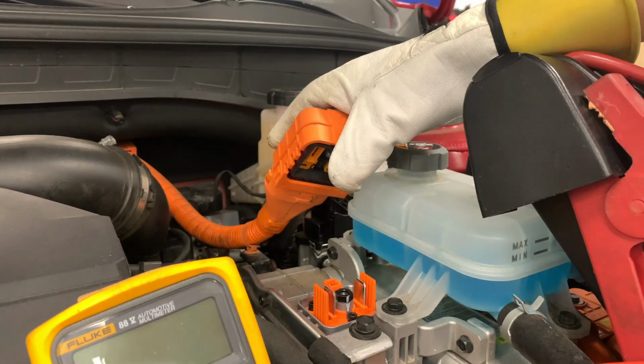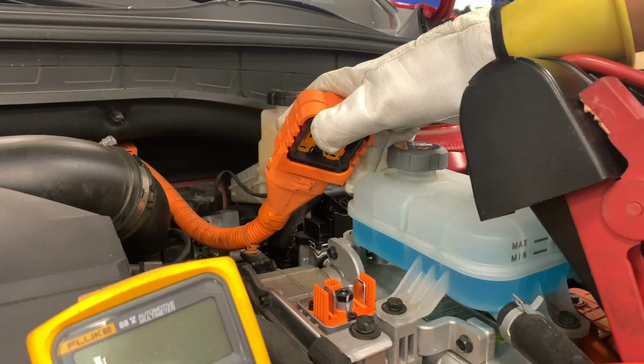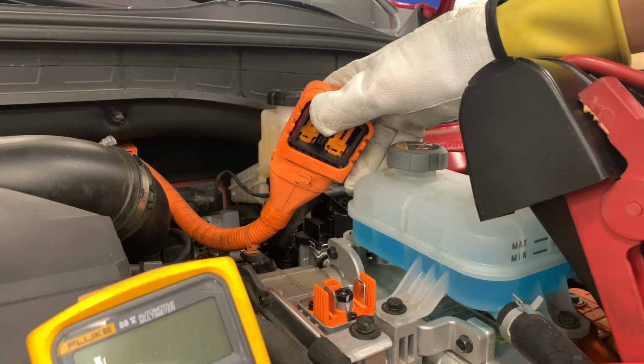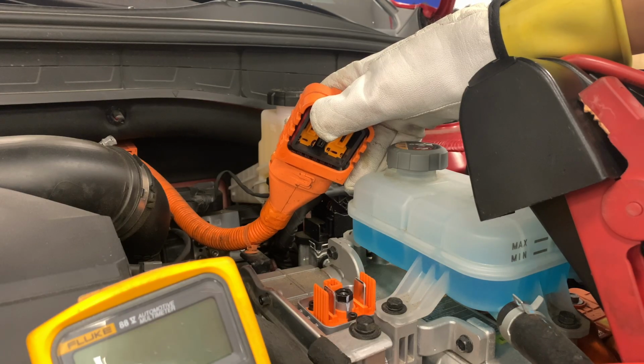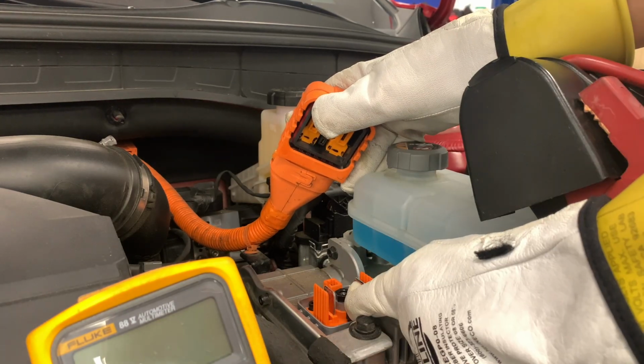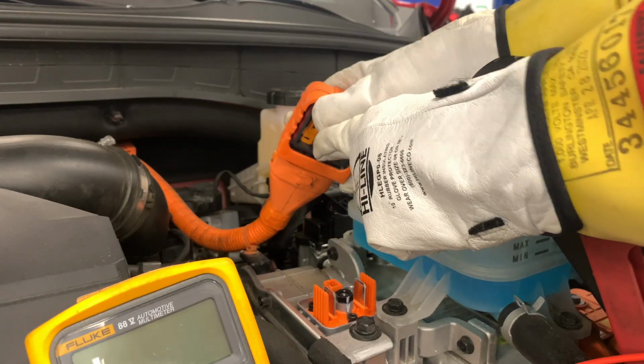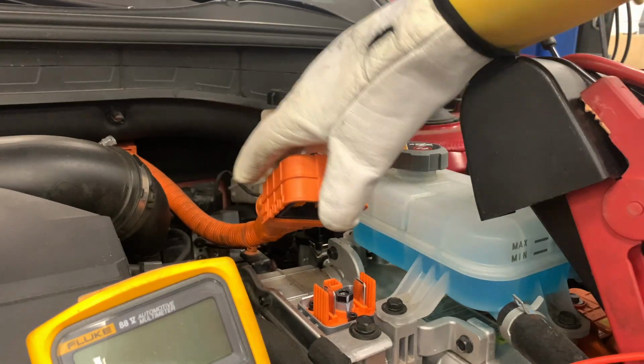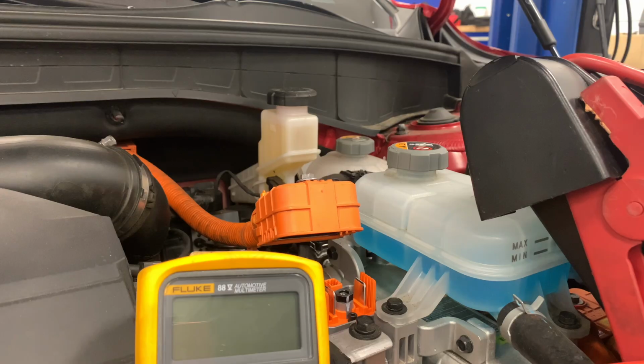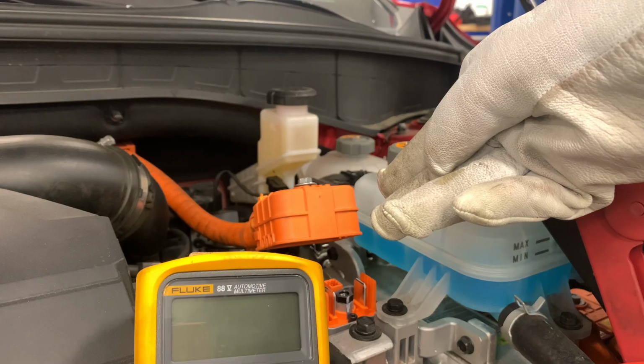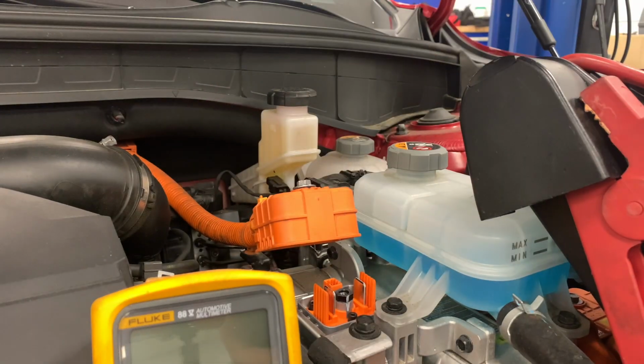Okay, so now we have officially accessed the high voltage system. Before we test this, we need to check not the vehicle, not the cable coming from the high voltage battery, but the meter itself. The reason is that if the multimeter isn't working properly and only reads 0 volts, you might check for high voltage and believe there isn't any, when in fact there might be, which could be extremely dangerous or even deadly.